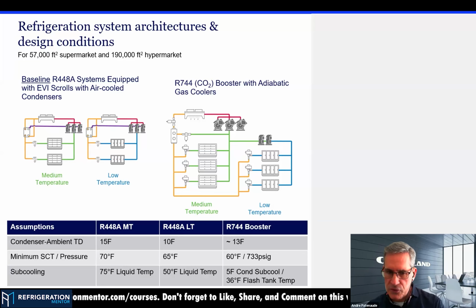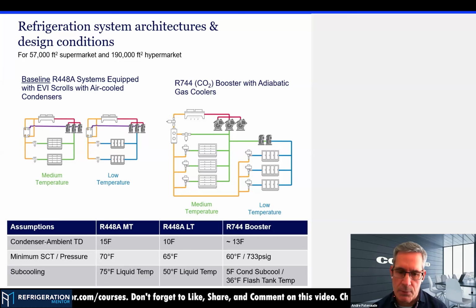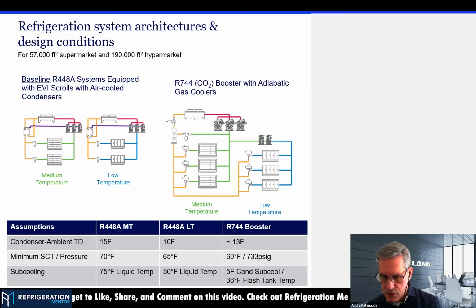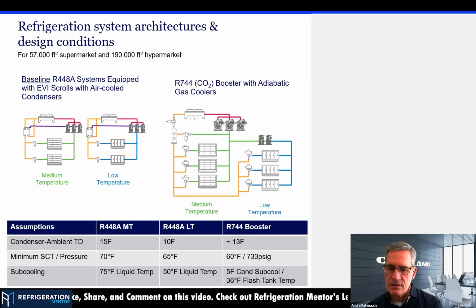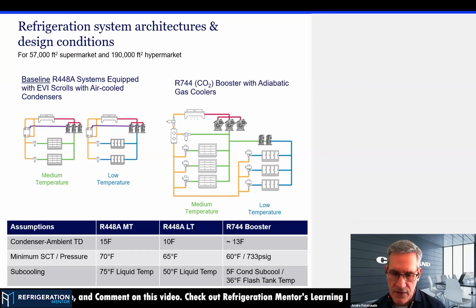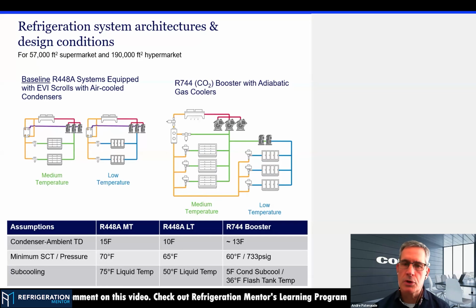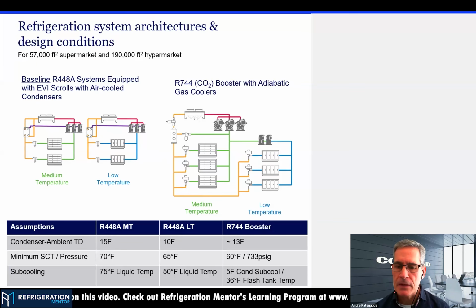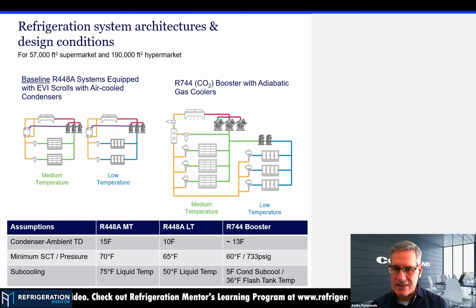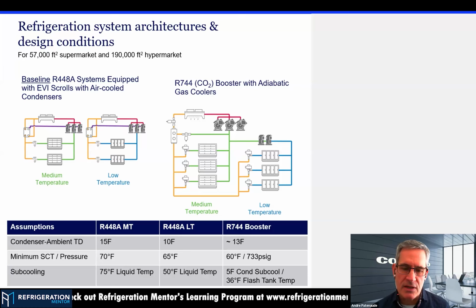So that's for medium temp. And low temp, you can see the numbers there, 10-degree TD, 65 minimum, and so on. And my booster, we've got our minimum condensing set at 60 Fahrenheit with 5 degrees subcooling and a 36-degree flash tank. So that's kind of the basic setup, and the capacities we'll build now.